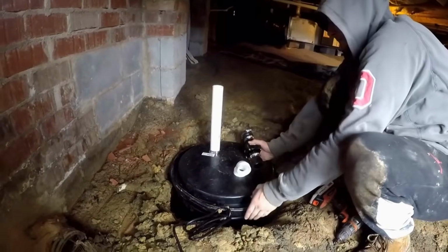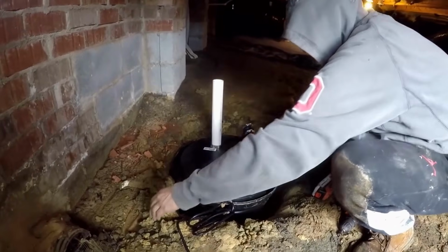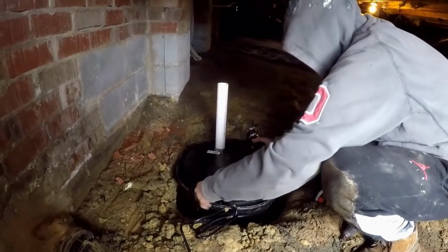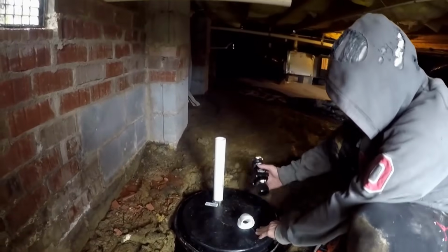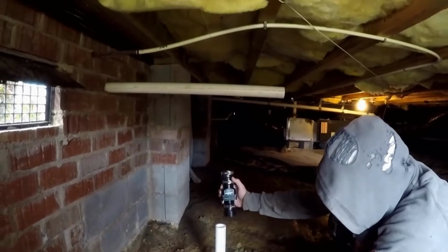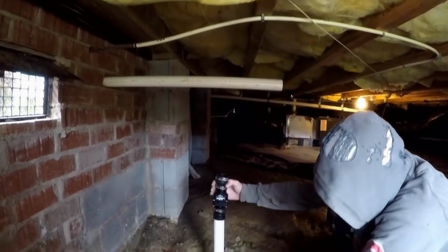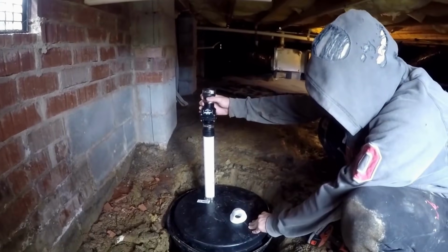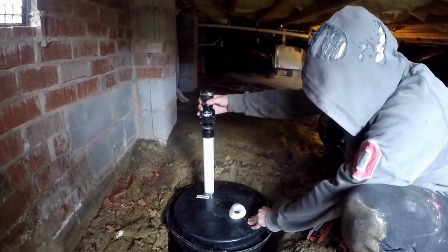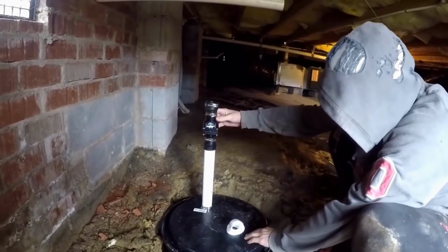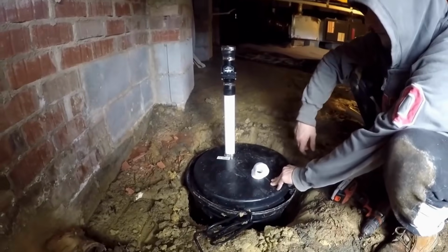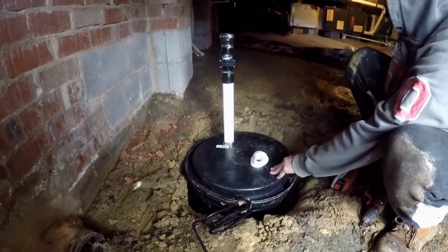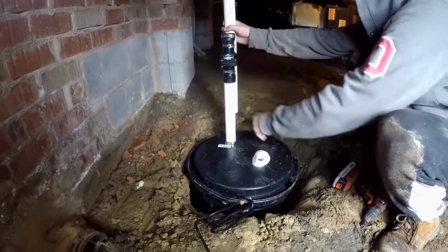So we've already set the pump down into the sump basin, into the pit, and now we're going to go ahead and put the check valve on. We wanted to make sure that it lines up with this horizontal discharge that we already pushed through the wall. So set your check valve on with your no hub, push it on good and tight. Notice that those arrows are pointing upwards, and the clamp that holds that together, we actually put that on the pipe real quick. We're going to pull that clamp up from the bottom.